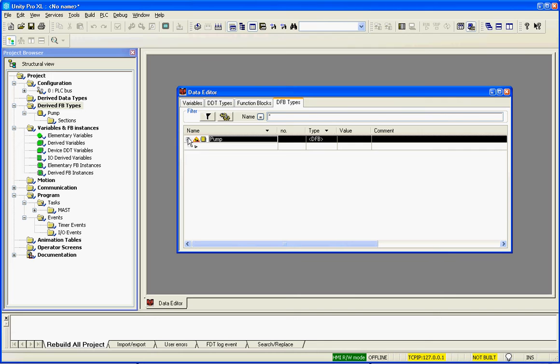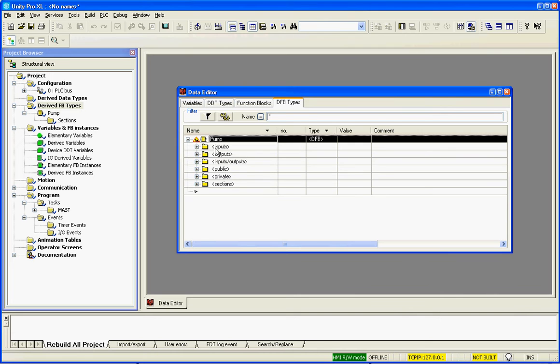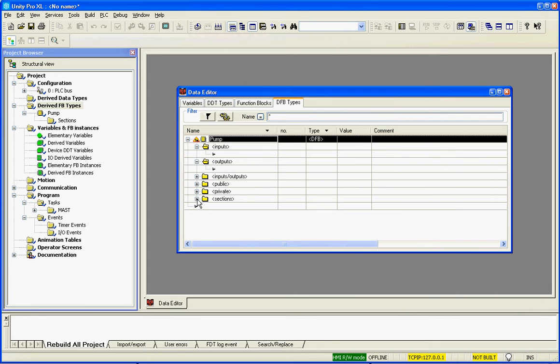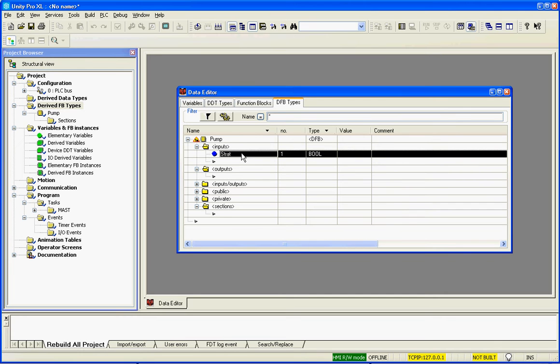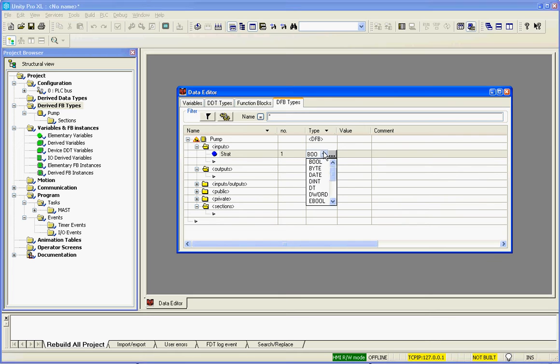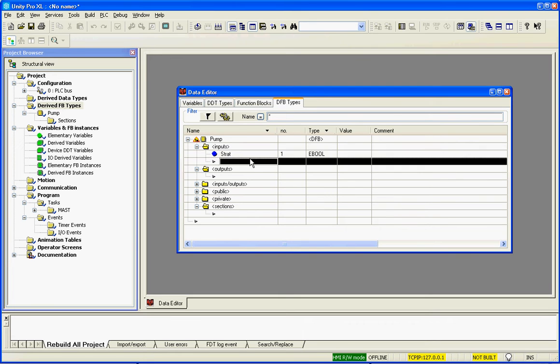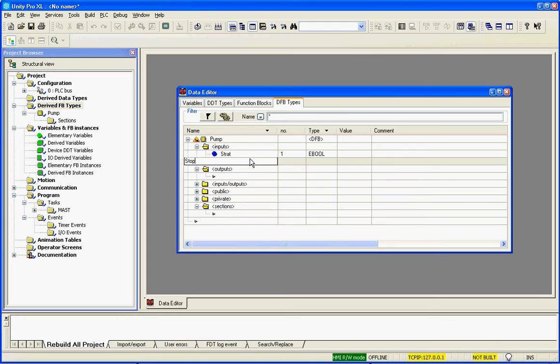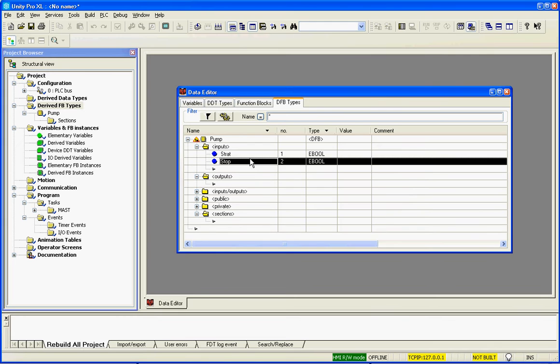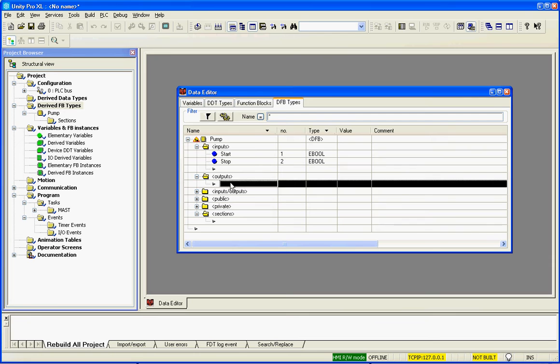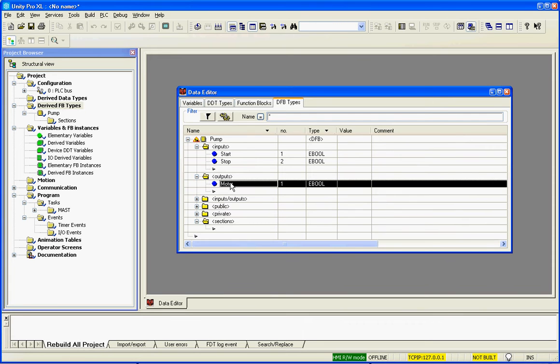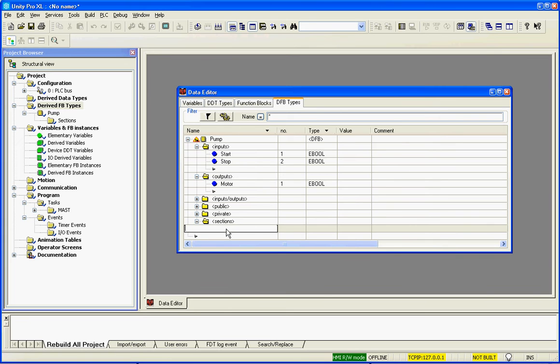Now within the derived function block we have inputs, we have outputs, and we have section logic. So we will create our start push button. We'll make that an extended boolean so we can attach, and then we put our stop. I'm going to re-spell start. And then I'm going to create my motor. So I've got two inputs and one output, and then we create our section of logic.